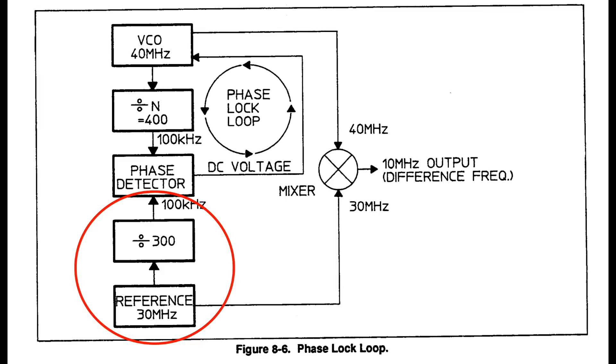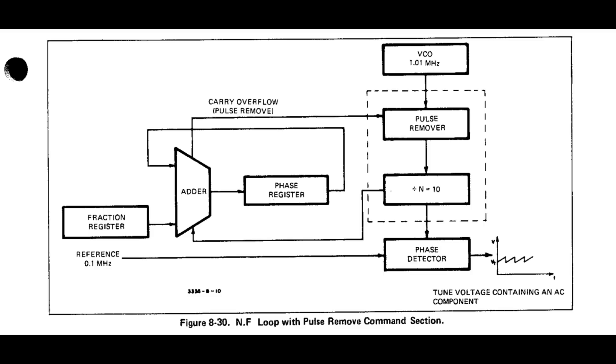The VCO is divided by a programmable number N, say 400 in our example. The output is N times 100 kHz, so 40 MHz. It is then mixed back with the reference to yield the difference, or 10 MHz. In this way, the 3325 can produce any frequency between 0 and 20 MHz in steps of 100 kHz by varying N. This is called the N loop.